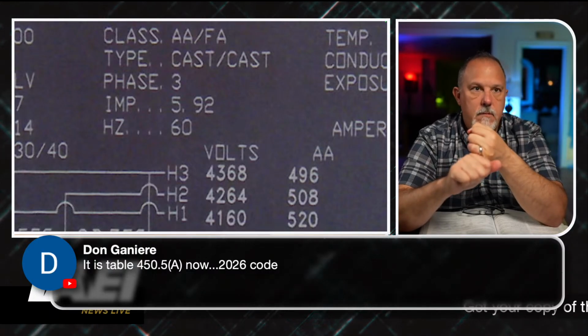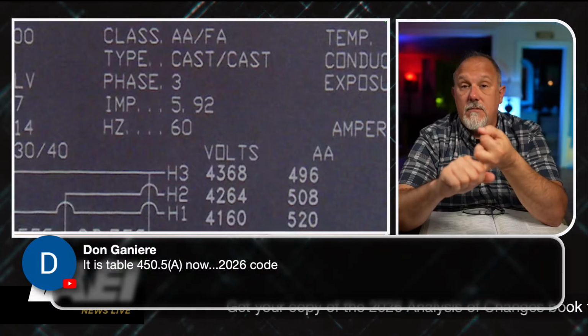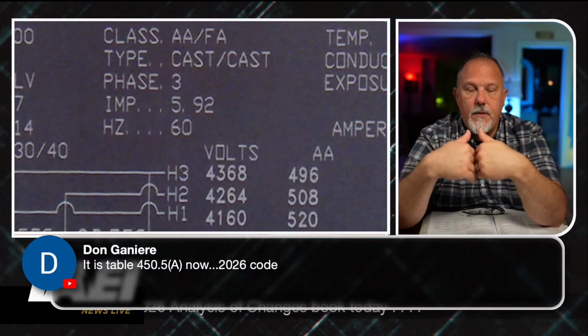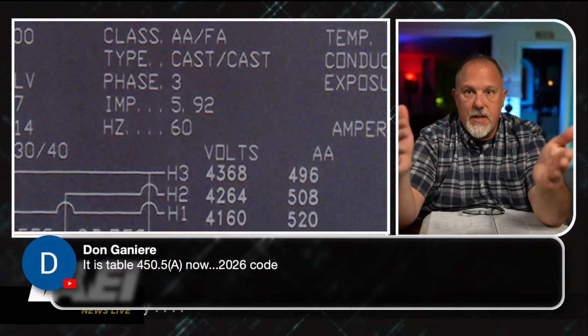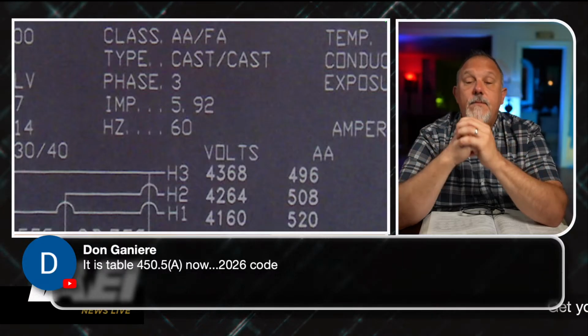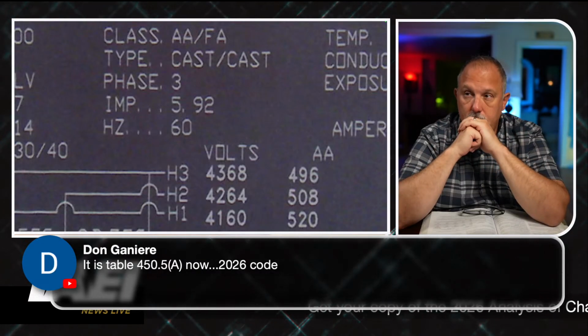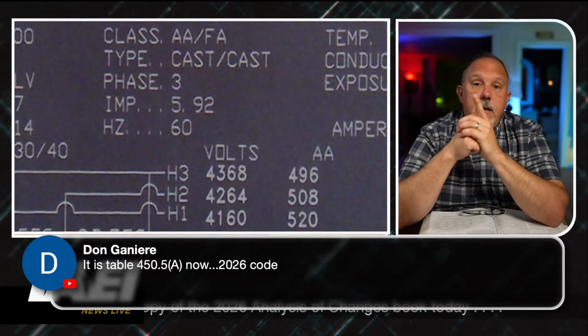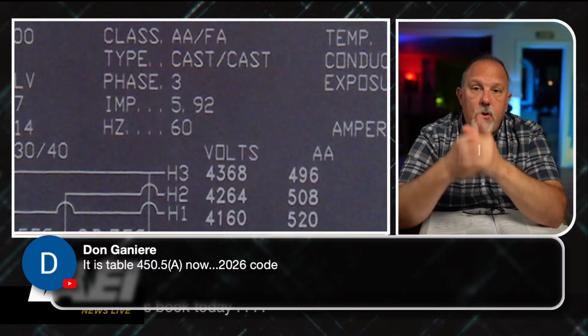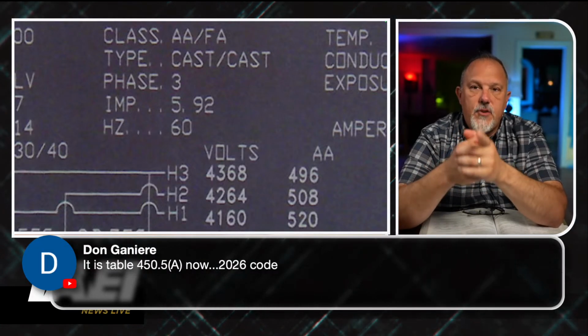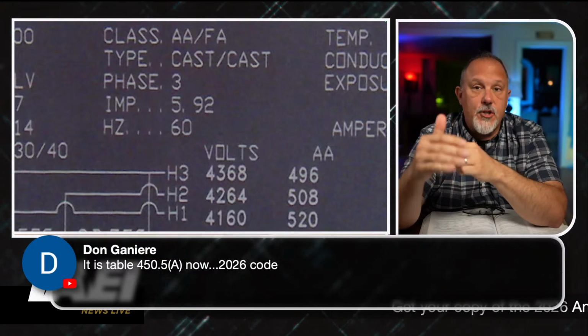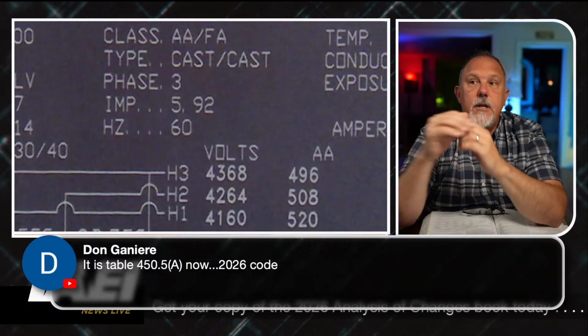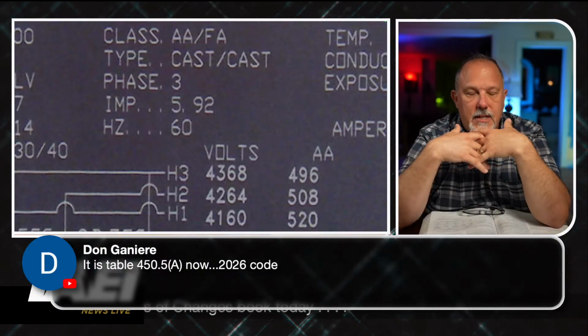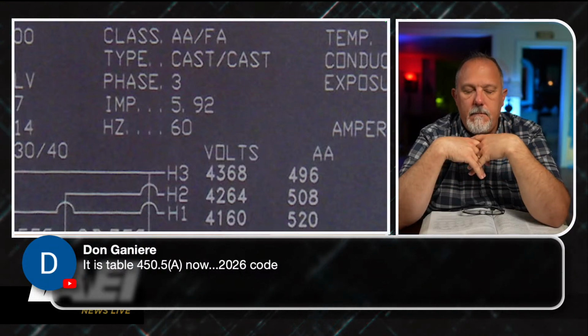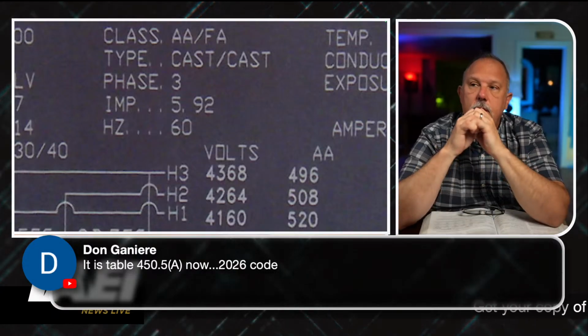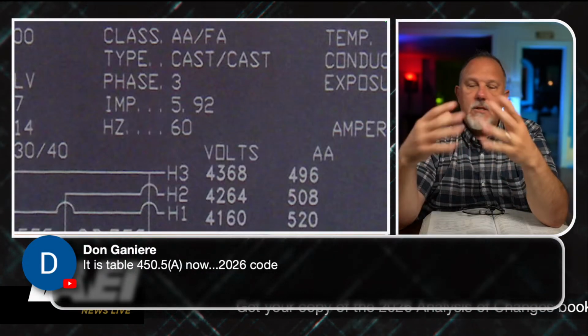Beyond that, I'm worried about short circuit protection, right? So that's why I have these maximum values, which hopefully you wouldn't go all the way up to 600% unless you've got, I don't know, there are probably reasons. But my overcurrent protective device has to permit the transformer to energize, and I'm going to see that inrush current regardless of whether or not I have a load on the transformer, because that's the magnetization. That's just getting all of the physics to happen, right? Hysteresis, the whole bit for the iron.